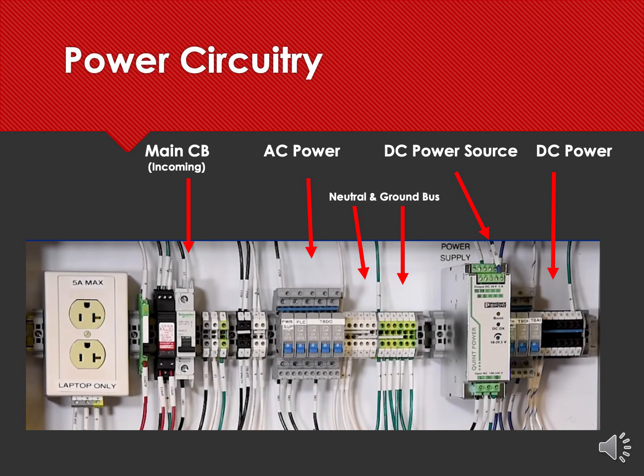Now again, this represents very legitimate shock hazards. I would recommend wearing rubber gloves if you're doing voltage testing or whatever on this side of the enclosure. And it also represents very low arc hazards on this particular system. With that said, if that incoming source was 480 volts, three-phase, this would all change. There could be very significant arc flash hazards in the panel. It's just this particular one does not represent significant arc hazards.